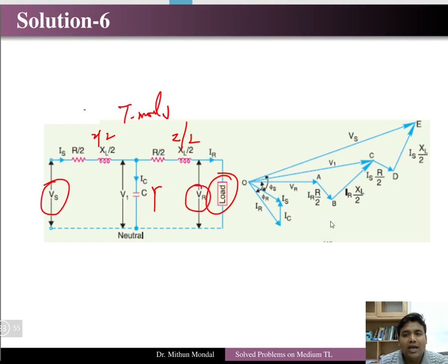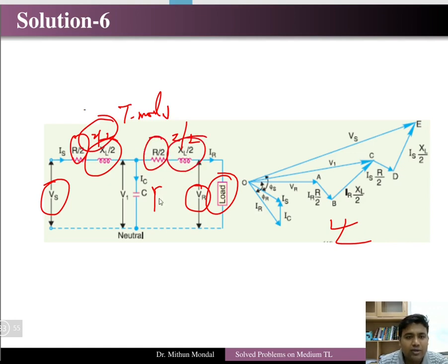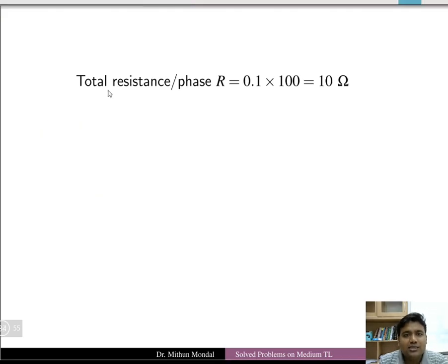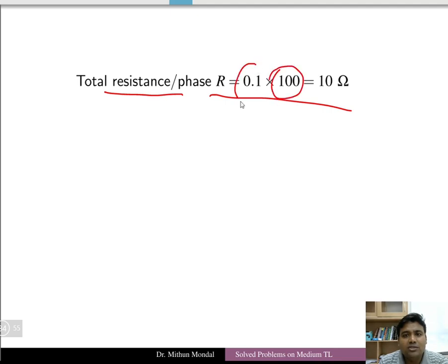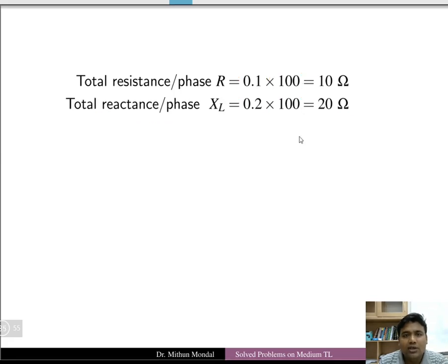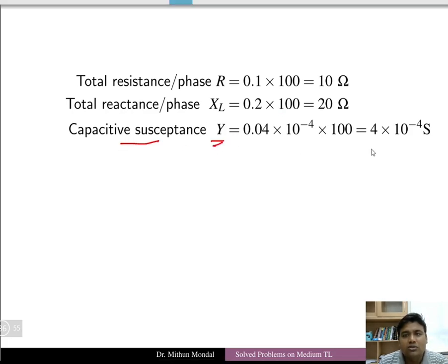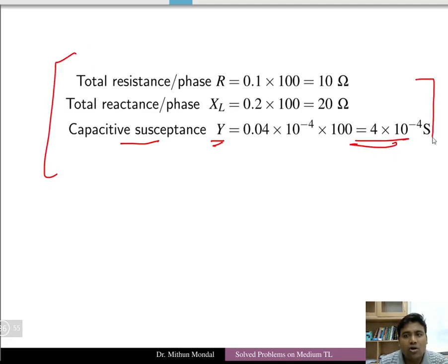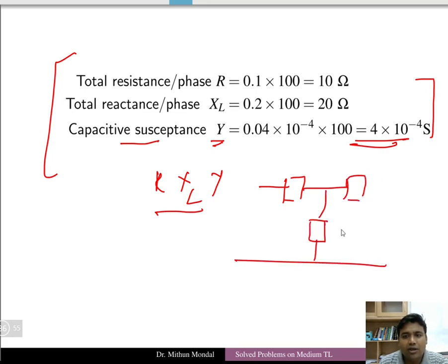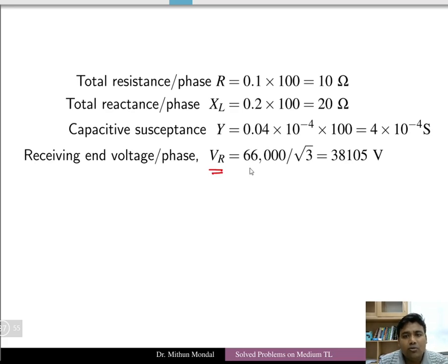In the nominal T model, the impedance is split as Z/2 on each side with shunt admittance Y in the middle. Total resistance per phase: R = 0.1 × 100 = 10 Ω. Total reactance: XL = 0.2 × 100 = 20 Ω. Total impedance Z = (10 + j20) Ω. The receiving end phase voltage VR = 66,000/√3 = 38,105 V.